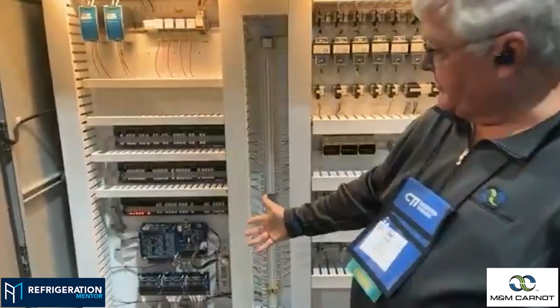This is our standard microprocessor setup that we've done, our version 4 micro. The IO racks go up for different things, lots of compressor IO, and all the analog signals come in the bottom for pressures and temperatures. With CO2 transcritical, it's a lot more instrumented than a normal ammonia or even cascade system would be.